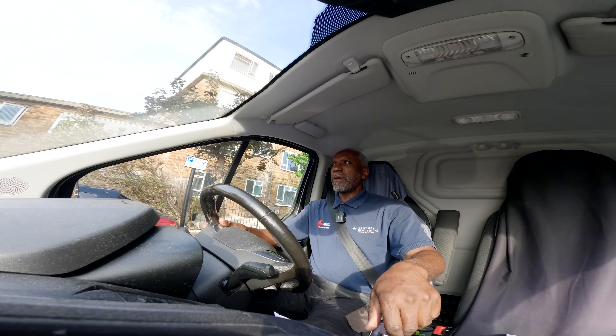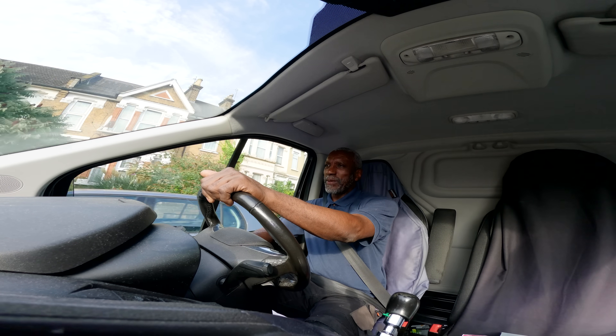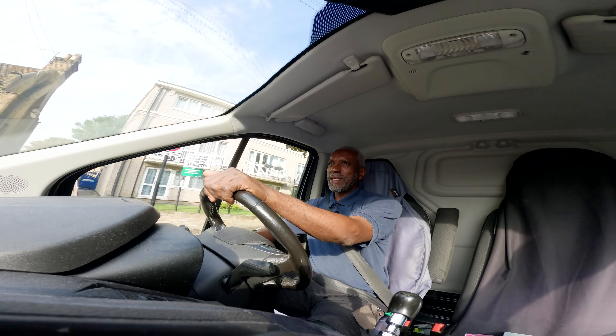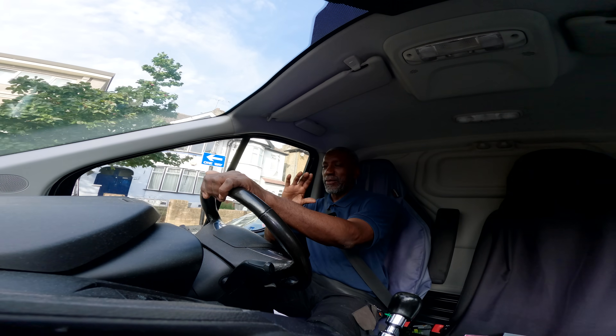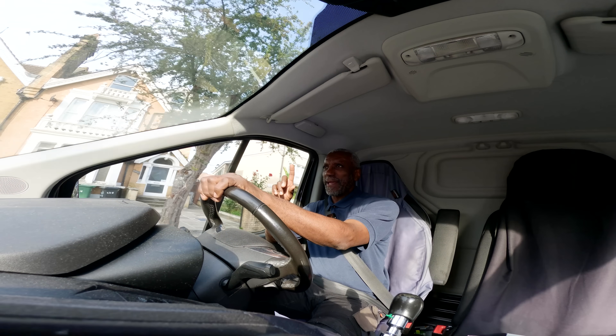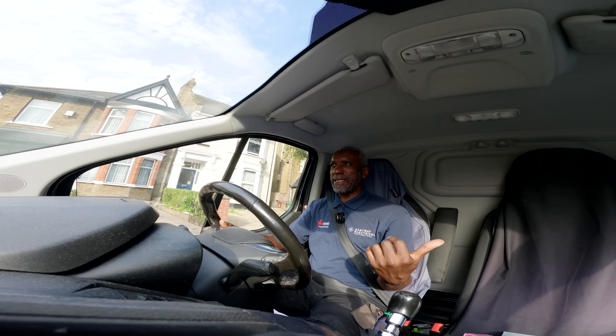Hi there, Daryl here again from Eastway. I'm off to a job that I've been to before — it was the house that we rewired and filmed and showed at the event at the cinema. I went there fault-finding first and ended up rewiring the whole house, apart from the loft area. There was a new loft conversion done a couple of years previous so that didn't need rewiring, but there's a fault up there. They've got a little fuse board in the loft area, supplied from the fuse board in the cellar that we put in, and they kept tripping the RCD in the cellar.